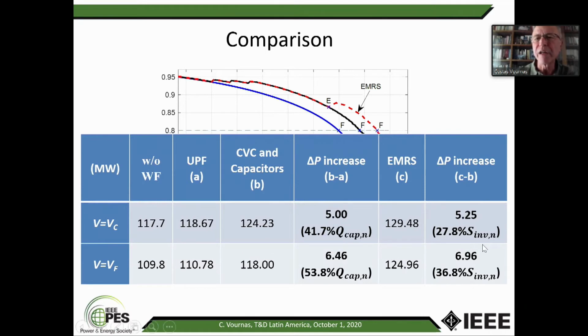And here, what I'm showing is the increase with the EMRS in percent of the available capacity of the wind farm. So you see, this 5 megawatt does not say much as megawatt, but it is about 30% of the nominal of the wind farm. And if I compare, that's for the maximum power, that's the voltage stability limit, VC. If I go with the low voltage limit, VF, I have a similar increase, even higher increase. And here you see the increase with the capacitors as percentage of the nominal megawatt of the capacitor. So you see the capacity is there because about 30% of the wind farm capacity can be given as extra transfer power in the weak corridor.